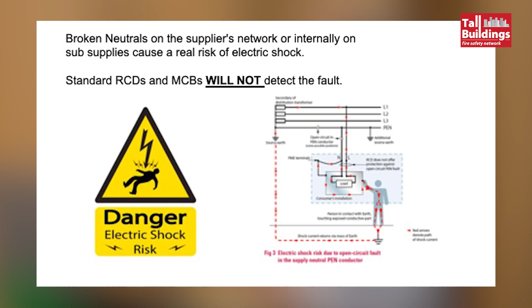Now in this instance, we put a break in it, and suddenly the neutral has got no way of getting back to the transformer. So it comes back down looking for a route back to that transformer. So it'll go into any earthing situation within that building. So it could be any type of metal work, it could be a railing outside the building, that will become live. So fire officers, for instance, if you've got those two dreaded things, electric and water, you've got a major problem for that chap if he touches something while he stood in water as well. So I will show you instances where this has happened around the world.